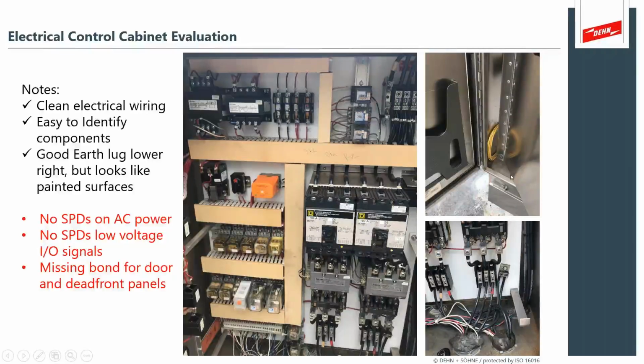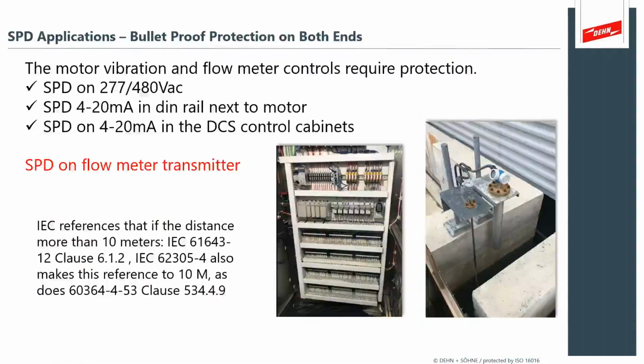Whenever you see a cabinet that's got something like a light on the outside of it, a control dial, well, that's an opportunity for it to be arcing to the door, and you must have that bond present for that safety, for that electrical apparatus. We see a lot of vibration control systems, motor flow meter control systems, and what's important, of course, is to have the SPDs on the power, but also on the data line that's often next to the motor control system, monitoring and doing its Profibus or whatever the CAN bus type circuits.